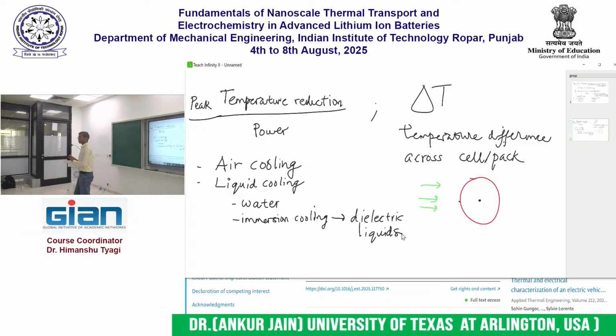Fortunately, dielectric liquids are not new. They have been used for cooling at least two other systems that I am aware of. One is computer chips — there are papers on taking a computer chip and, instead of cooling it with a heat sink or fan, blowing a dielectric liquid over it directly. The dielectric liquid can touch all the wires and connections without causing a short. There are some well known dielectric liquids; the one I am most familiar with is called FC72. You can easily buy FC72 and get started, and it's not very expensive either.